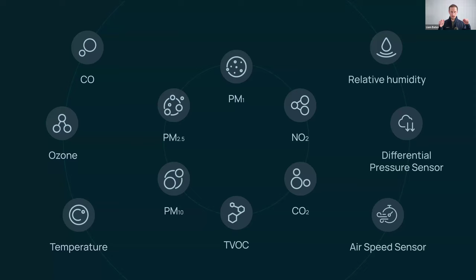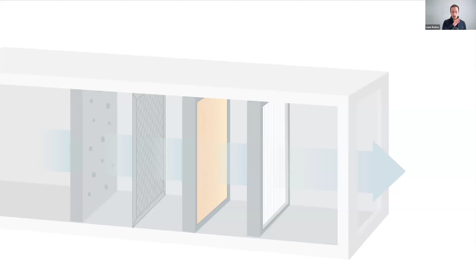So we know that building engineers need more than just air quality data, right? When you're trying to go from understanding what is happening in a space to why, you need operational data, data that you can use in your day-to-day work. And this filter efficiency kit adds two new sensors, differential pressure and airspeed. So you can install one probe before the filter and another probe after the filter and be able to look at the differential pressure between those. You can also look at the reduction in PM 2.5 readings.